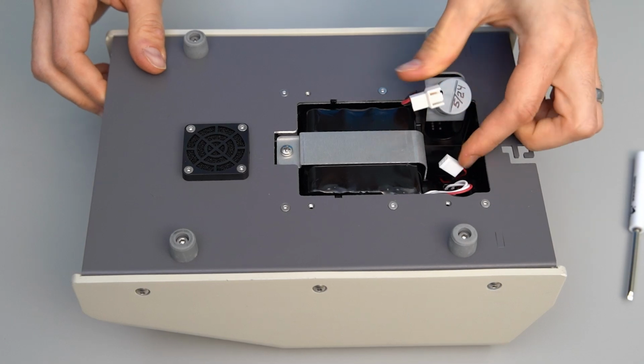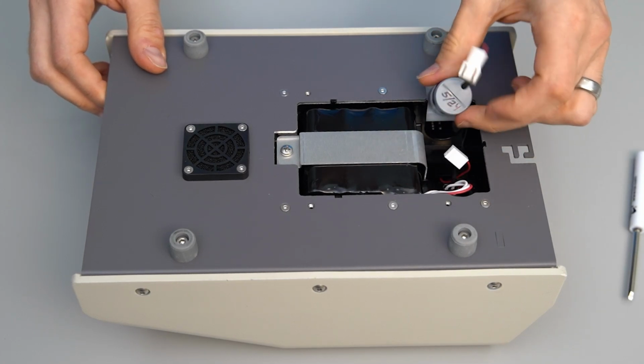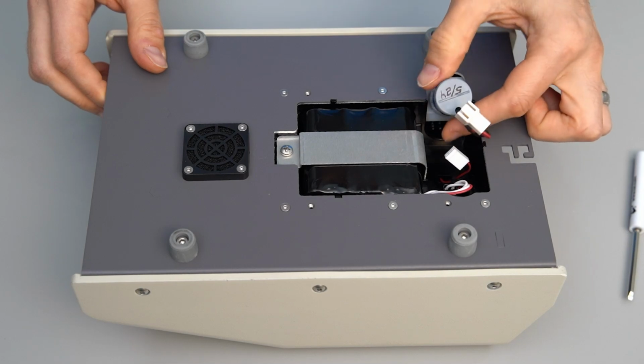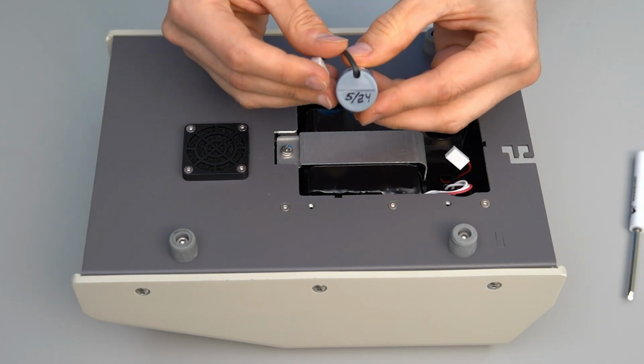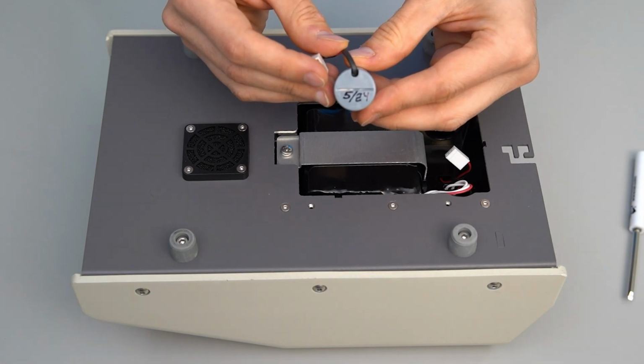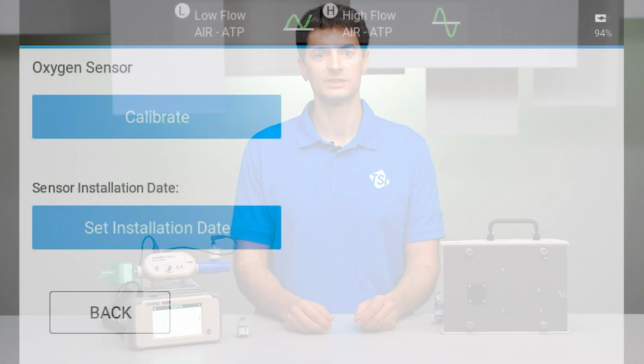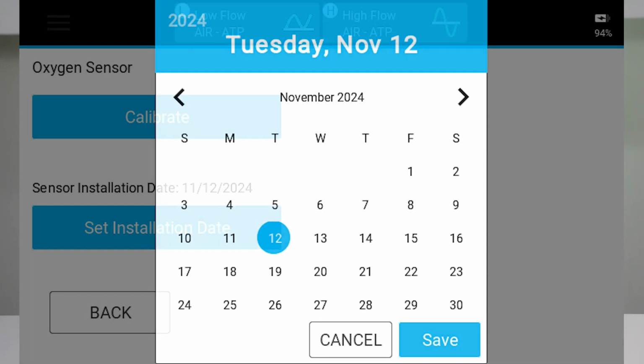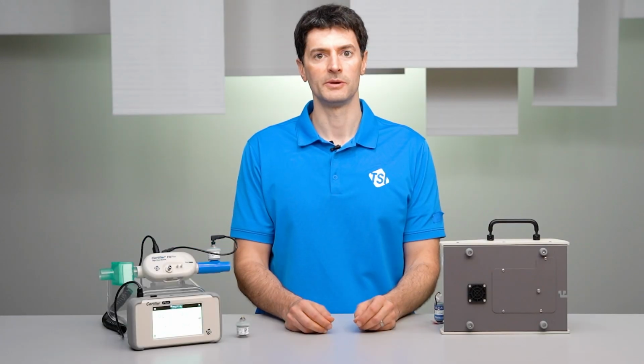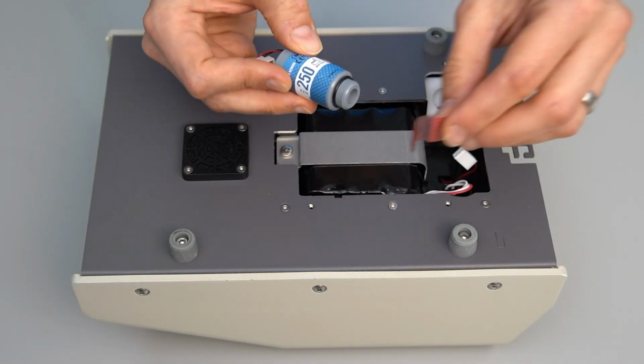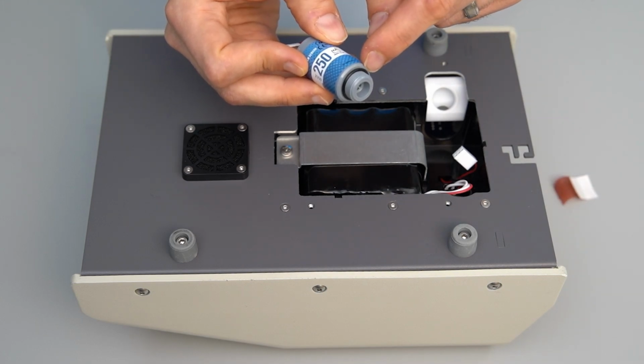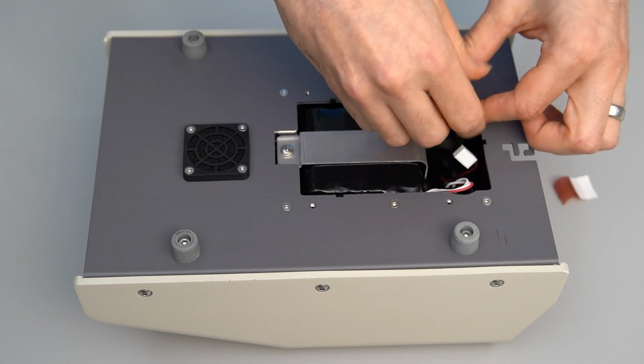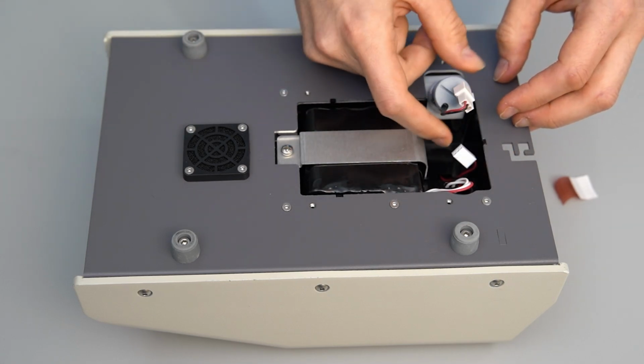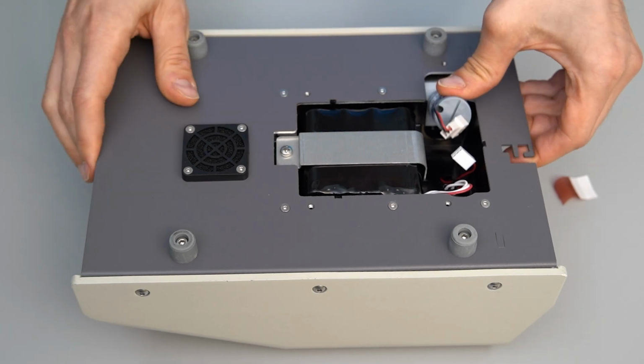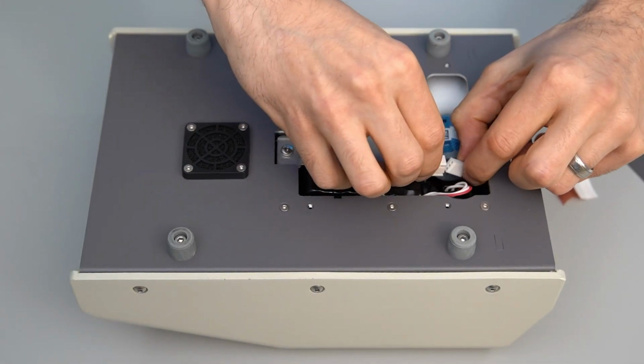When the sensor is installed at the factory, TSI will write the month and year of installation on the oxygen sensor. You can do this yourself when installing a new sensor, and you also have the option to record the installation date on the Certifier interface from the oxygen sensor screen. To install the new sensor, remove the occlusion tab and ensure that the O-ring is present on the threading. Screw the sensor in by hand, push it down into the instrument cavity, connect the pigtail, and then reattach the bottom cover.